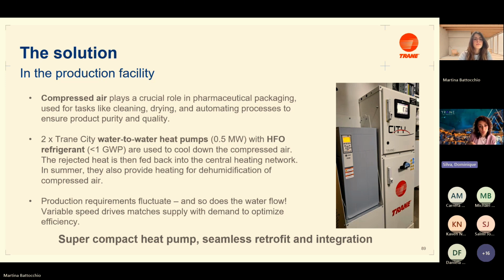So what we worked with them to do was install 2 water-to-water heat pumps with a total capacity of 500 kilowatts, using an HFO refrigerant with almost 0 GWP. We're using these heat pumps to cool down the compressed air, but rather than rejecting that heat to the ambient or a nearby source, we feed it back into the central heating network nearby.